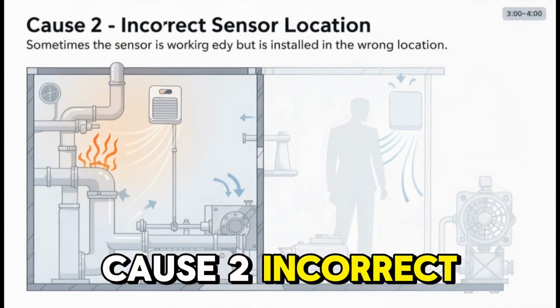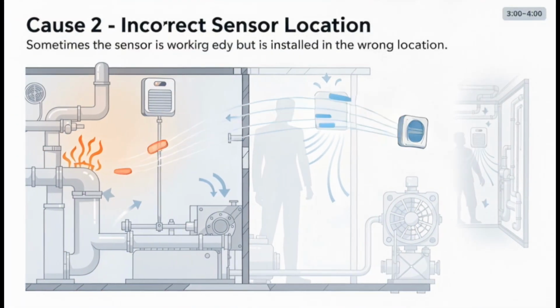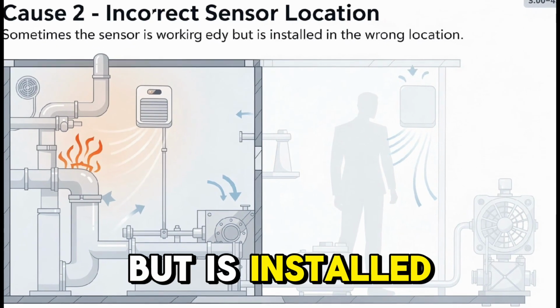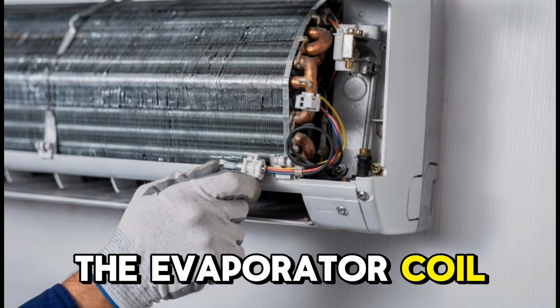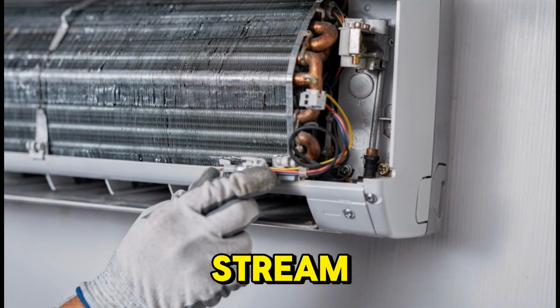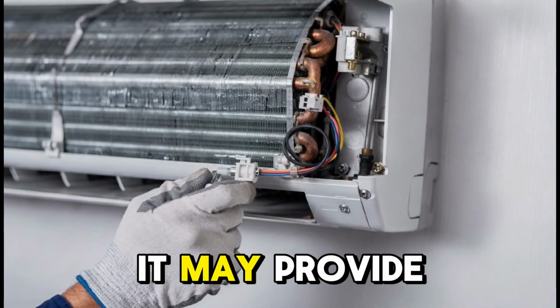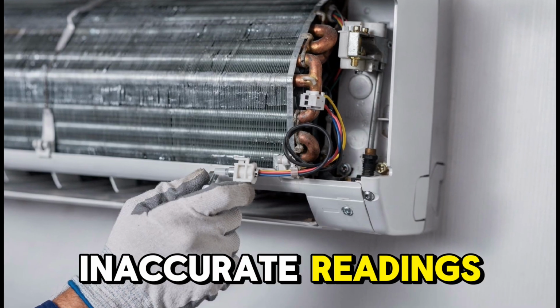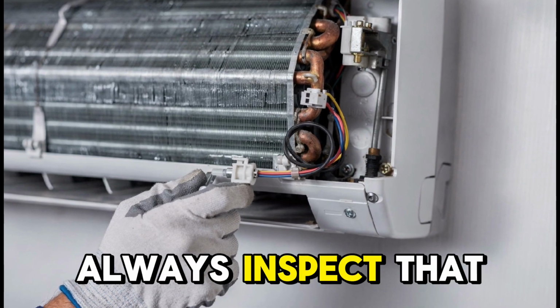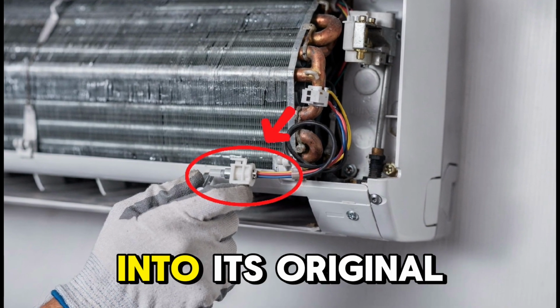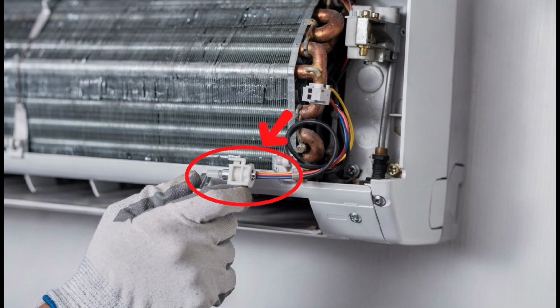Cause 2. Incorrect sensor location. Sometimes the sensor is working perfectly, but is installed in the wrong location. If it's touching the evaporator coil or cold air stream instead of sensing room air, it may provide inaccurate readings. Always inspect that the sensor is properly clipped into its original position.